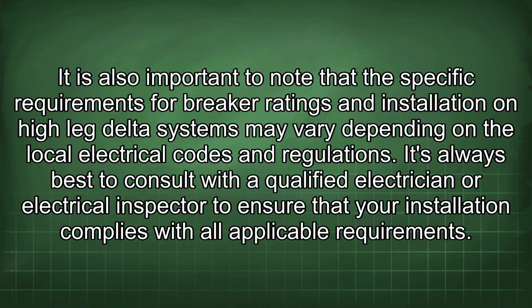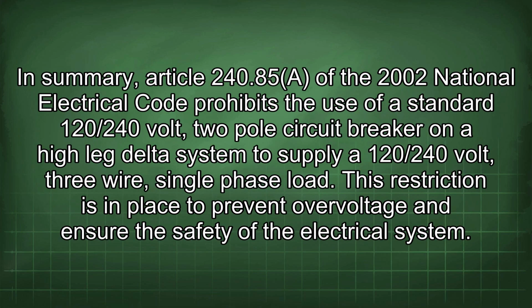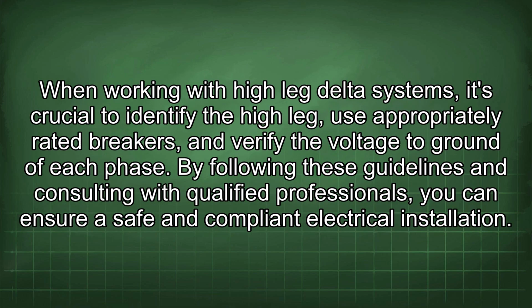In summary, Article 240.85 of the 2002 National Electrical Code prohibits the use of a standard 120/240 volt 2-pole circuit breaker on a high-leg delta system to supply a 120/240 volt 3-wire single-phase load. This restriction is in place to prevent overvoltage and ensure the safety of the electrical system. When working with high-leg delta systems, it's crucial to identify the high leg, use appropriately rated breakers, and verify the voltage to ground of each phase.